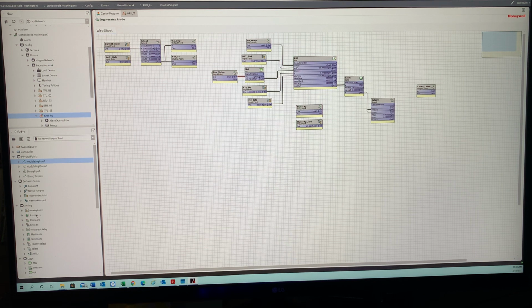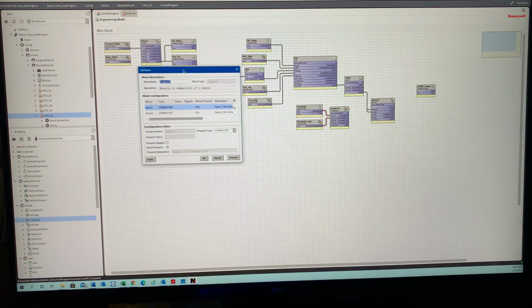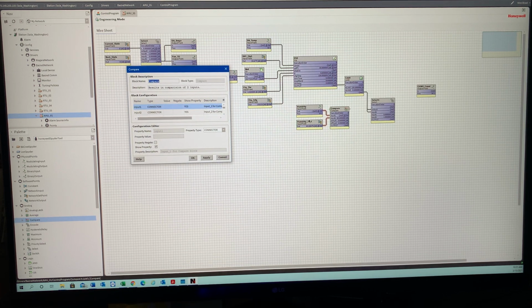We're going to grab a compare block, take our humidity output into the input, and the set point. Then we go into configure properties and say if our humidity is higher than our set point, then we're enabled. There's also an on and off hysteresis, which lets you do it based on a value.